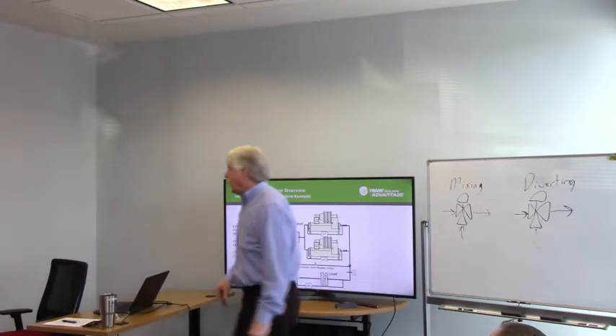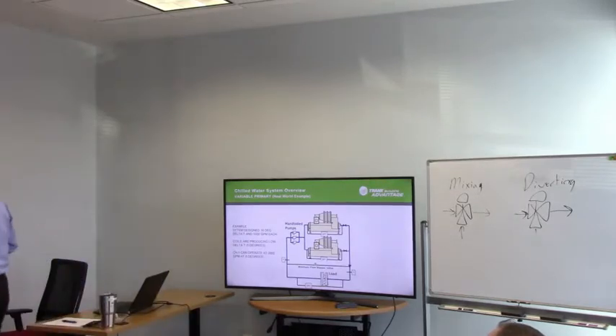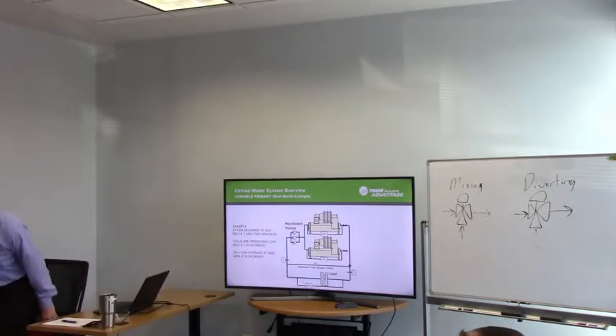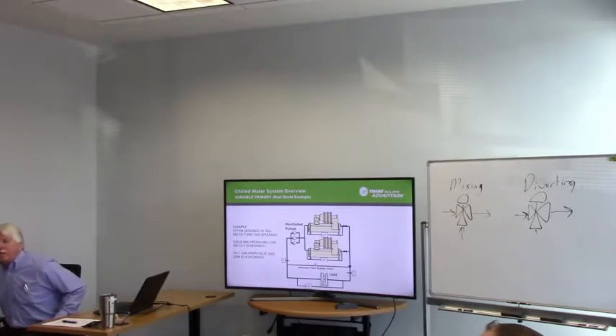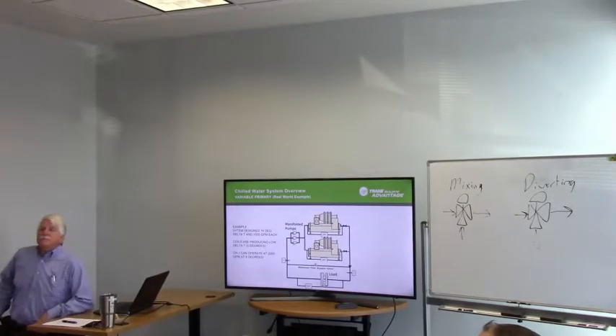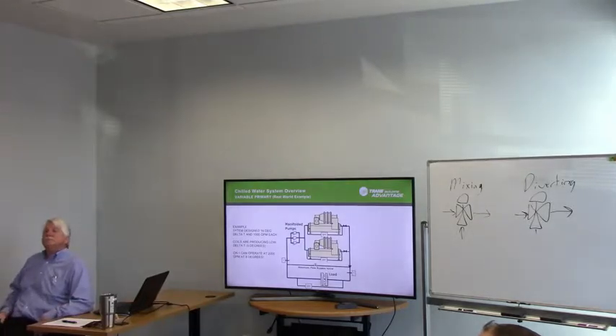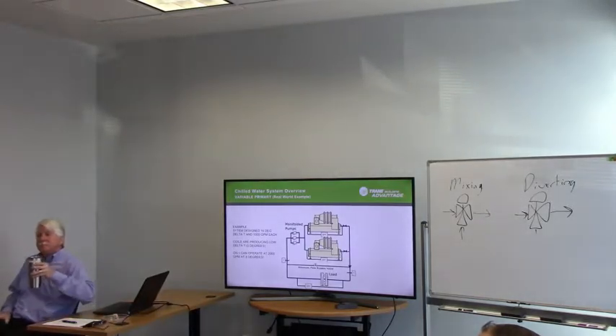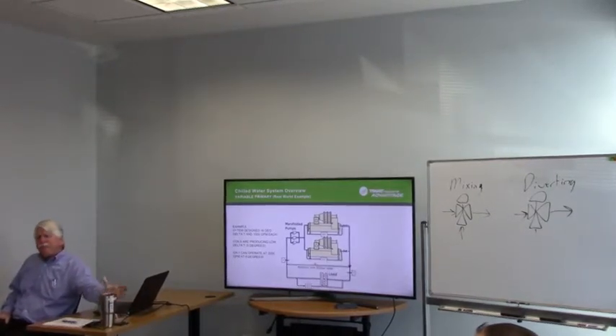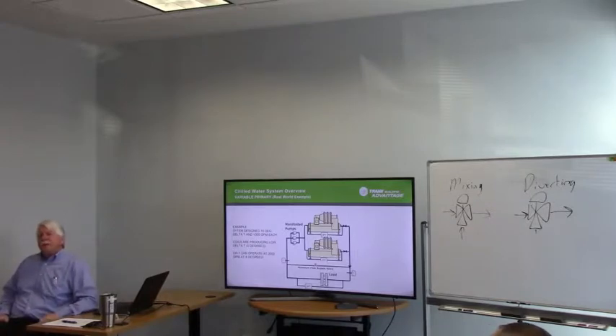Hey Jake, one thing that came up that Kevin was talking about was why don't we use faster acting actuators on the bypass valve? Yeah, so right now, there's really two main options that we go with. It's the SR or the MFT. The MFT can be programmed for, I believe, 8-second drive time or 10-second drive time on the low end. The SR, I think, standard is 90-second drive time. The SR tends to be simpler on the install side. 90 seconds might not be fast enough. We haven't really discussed that, I don't know.